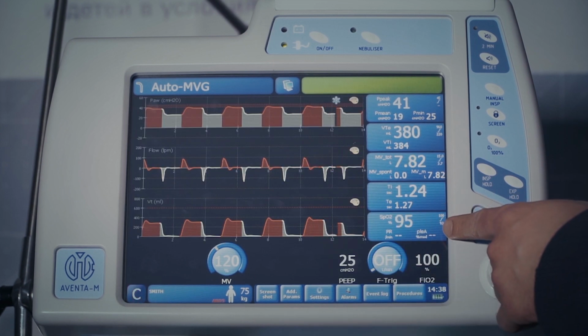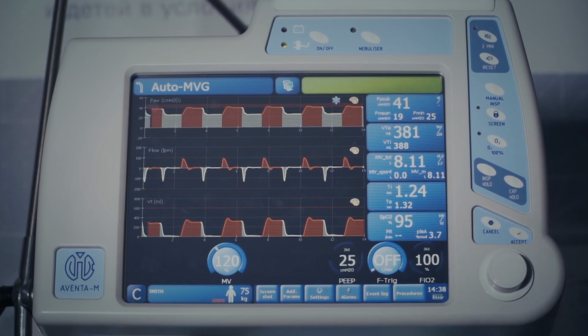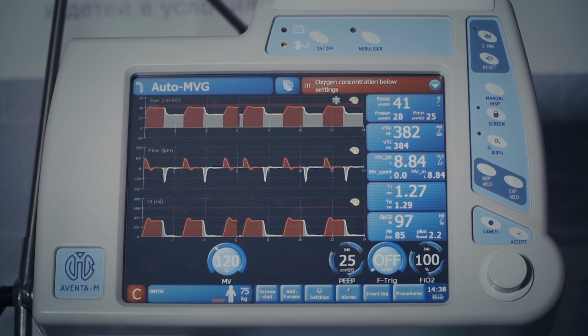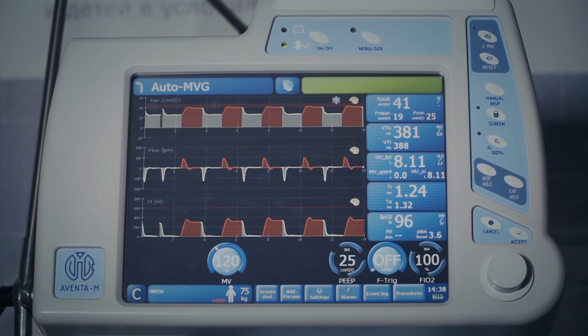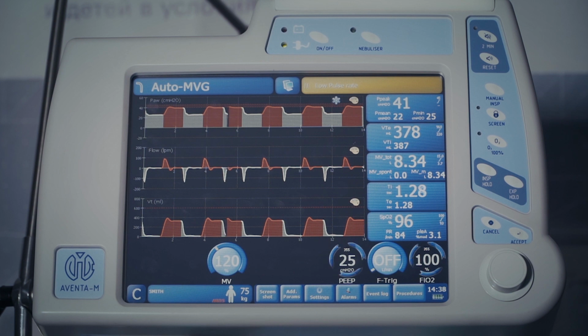If your ventilator is fitted with pulse oximetry sensor, open System Settings and go to tab Auto. Activate buttons of Automatic Control FiO2 and PEEP. Based on the pulse oximetry sensor readings, the ventilator will start to gradually increase or decrease the specified parameters in accordance with the protocol recommendations.